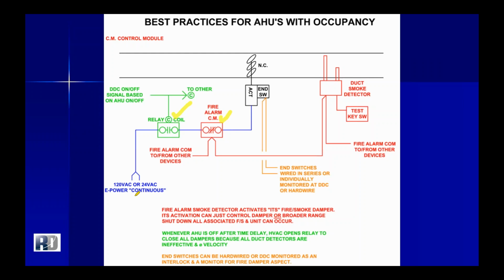And again, as Rachel has indicated, the end switches are there. We believe that they're important to be utilized, whether or not you are going to use them for control or at least monitoring them to know that they are opened or closed. There is always the decision of which end switch do you monitor. Do you monitor them both, or do you monitor the end switch that proves that the damper is really closed, the one that would change the state at around the 10-degree mark, or do you use the other contact, which changes state at around the 80-degree rotation mark?